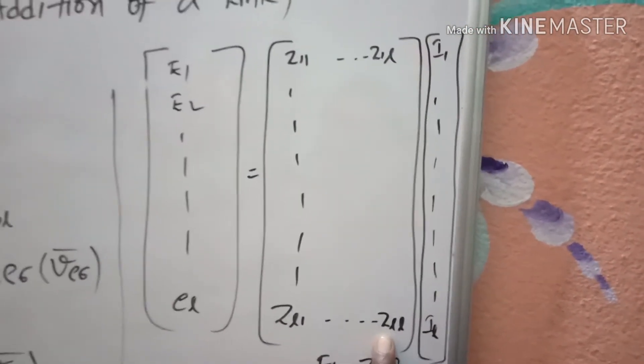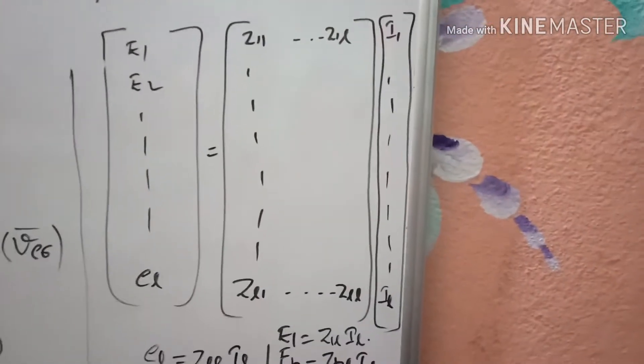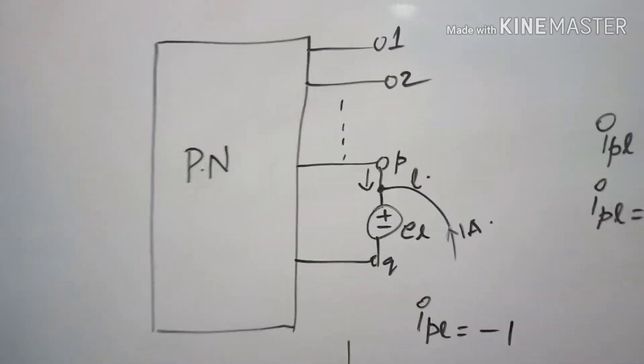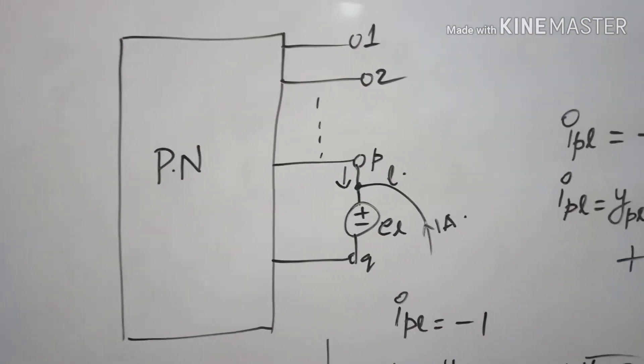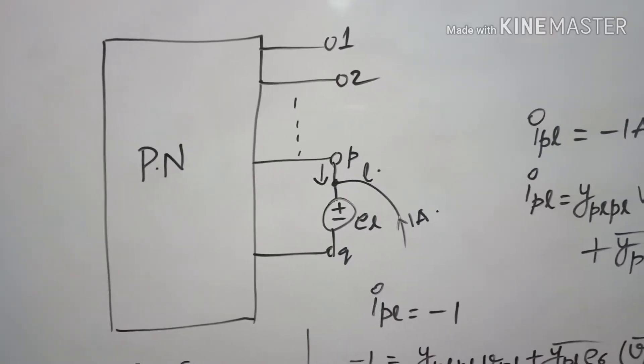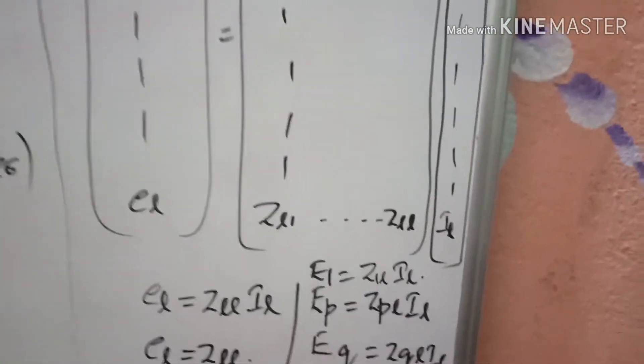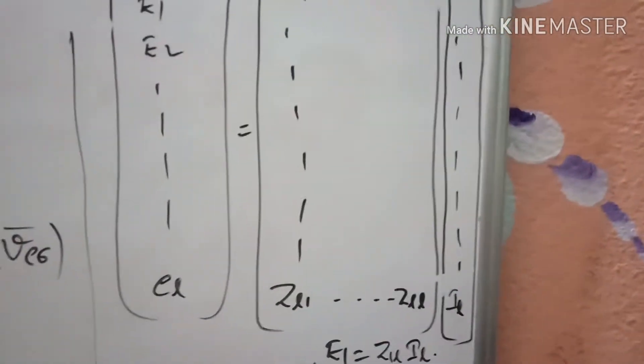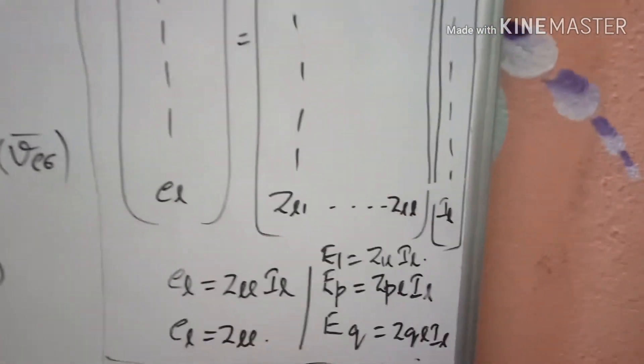This is the Z_ll value. What I need to do is inject a current of one ampere at the lth node. The lth node is nothing but a fictitious or imaginary node between nodes p and q. If I inject a current of one ampere at the lth node, making all the remaining currents as zero, I will get e1 as Z_1l into il.